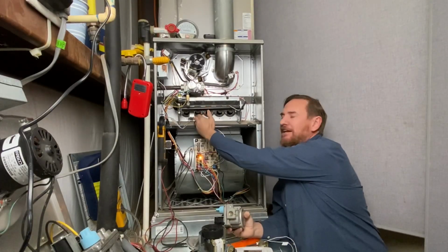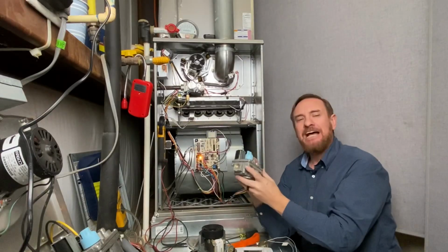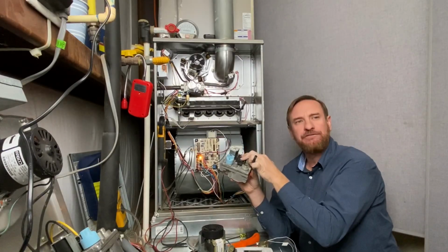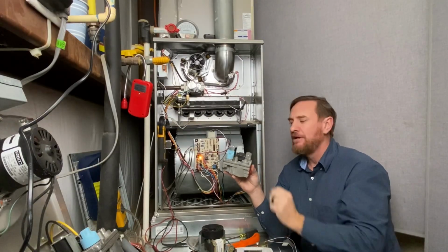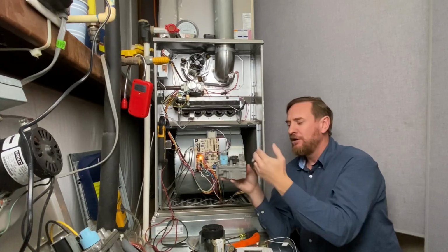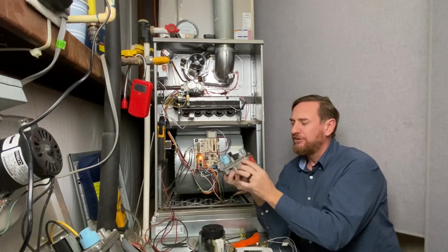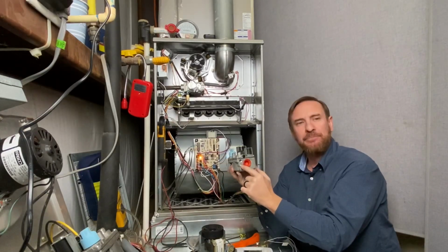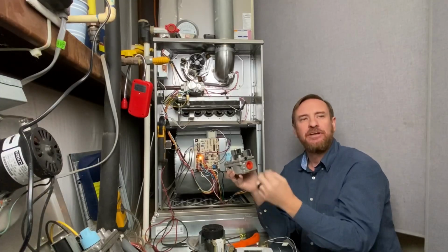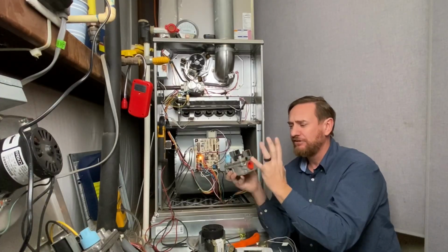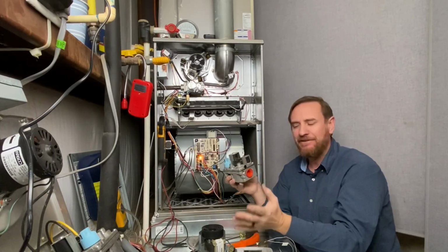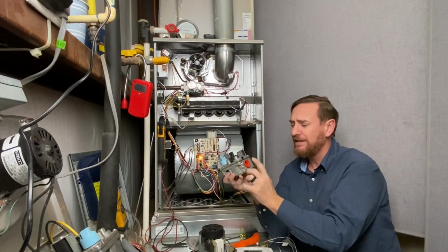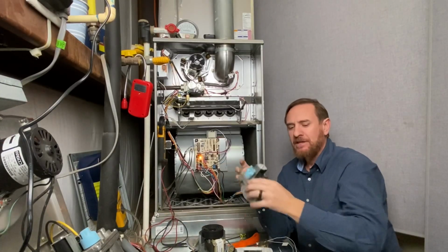So after we get our hot surface igniter lined up, we only have a few seconds that we're going to get 24 volts to this gas valve for it to open. Once we see that this valve's opening, we can look at the pressure. Most all of these gas valves have an output pressure port that we can check. All different types of manufacturers, all different ways of doing that. Refer to the manual to see if you're doing it the correct way, but it puts out output pressure.